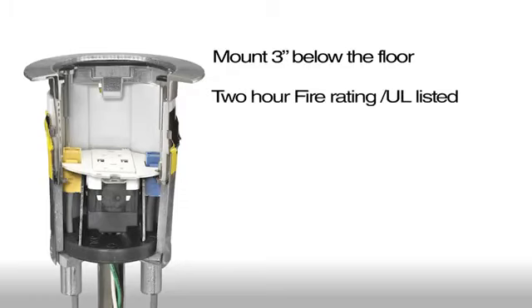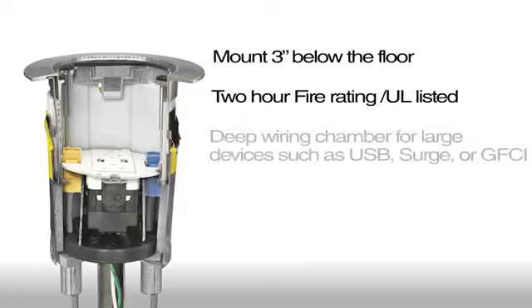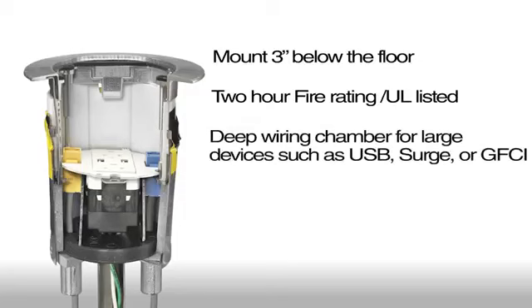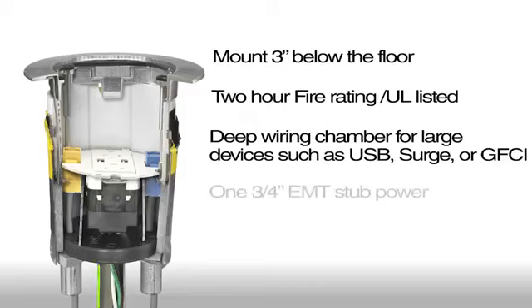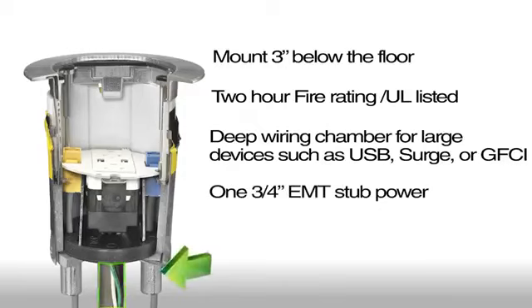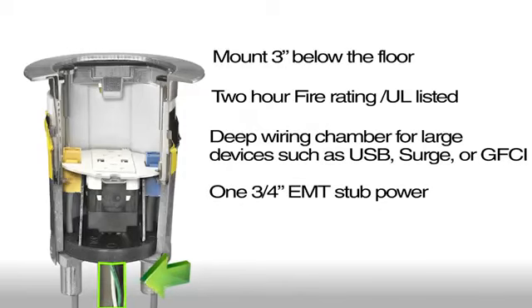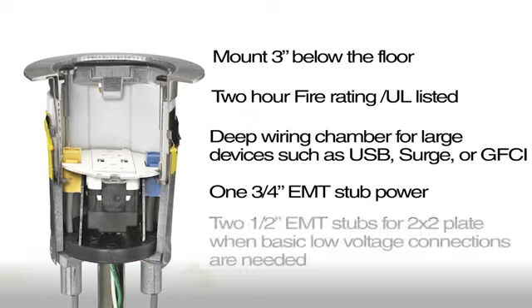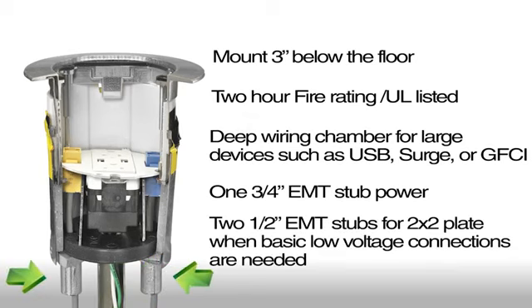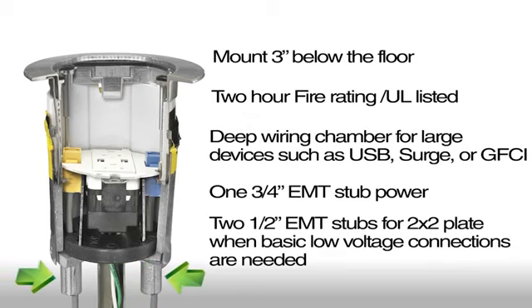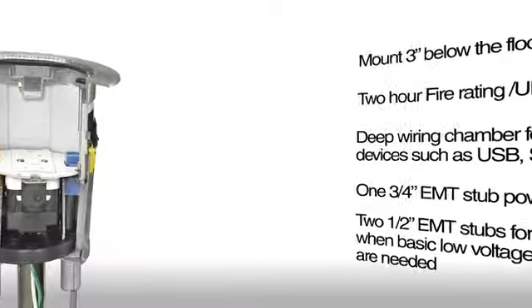The fitting has a 2-hour fire rating and is UL listed. Deep wiring chamber for large devices such as USB, surge, or GFCI. One 3-quarter-inch EMT stub for power. Two half-inch EMT stubs for 2x2 plate when basic low voltage connections are needed.